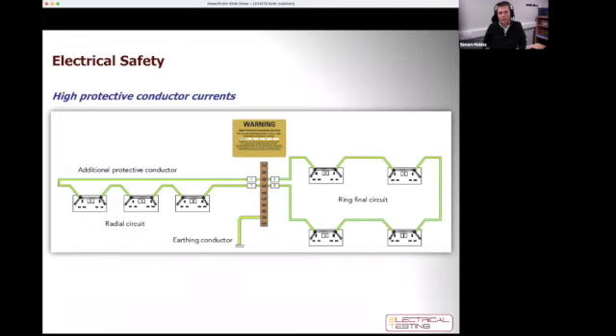And whilst the level of leakage current in a typical domestic premises is unlikely to be a problem, in other types of installations, such as those comprised of a large number of electronic devices, the earth leakage currents can become quite high in magnitude and present quite a risk of electric shock if the circuit protective conductor becomes disconnected. So equipment having a protective conductor current exceeding 10 milliamps should be connected to the supply by the methods laid out in BS 7671. Essentially that means that the protective conductor should be oversized or another protective conductor run into the circuit. What we can see on the image in the current slide, on the radial circuit on the left-hand side, is that it's had an additional bond run back from the last socket to the main earthing terminal. If this was not the case, then it's possible that anything metallic became energized at a dangerous potential.